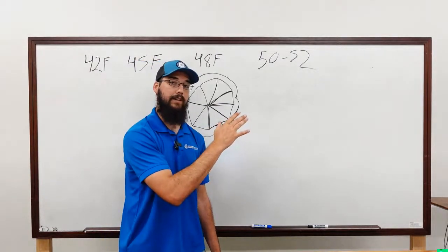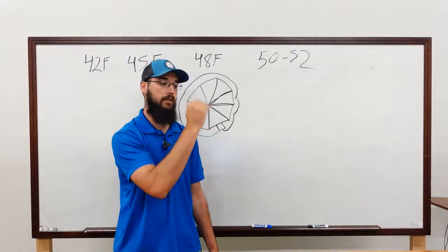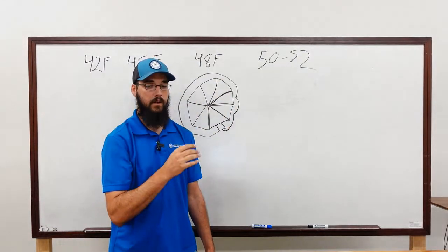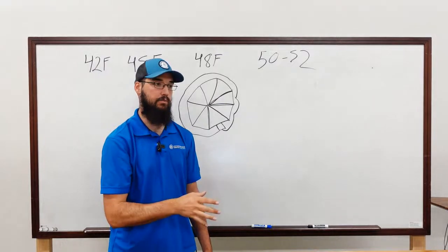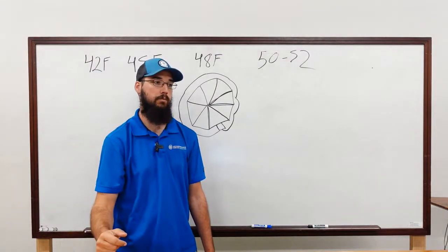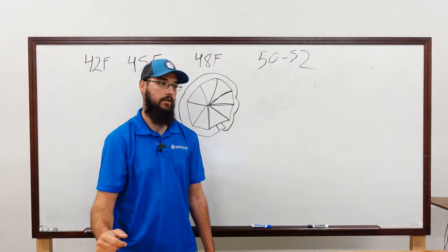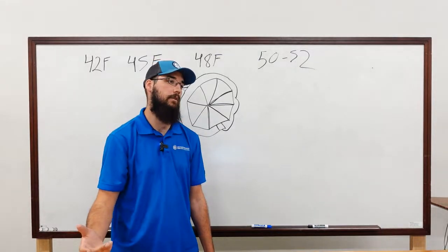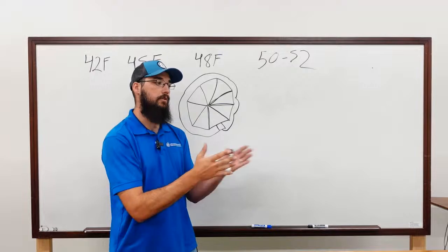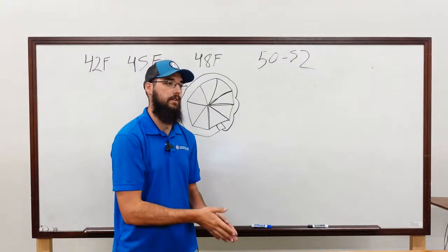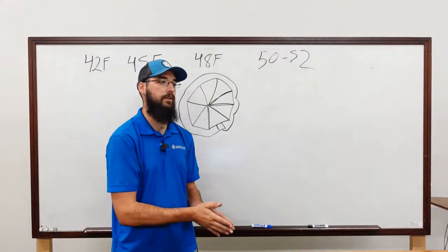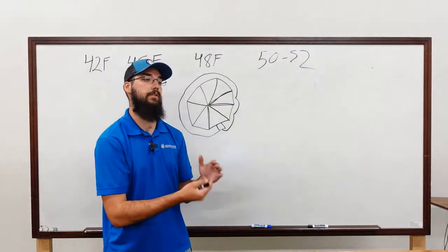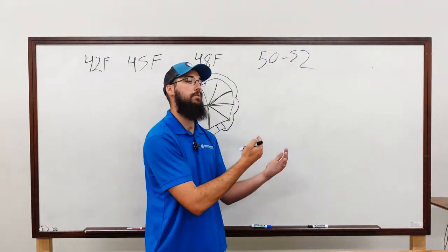And if it didn't have that limiter, it would literally pull the suction pressure down to the point of tripping a low pressure safety. Well, it wouldn't be closing the metering device. You'd literally pull down to the point of tripping safety, so your low pressure switch would trip. So that suction limiter is another thing that can help protect us.